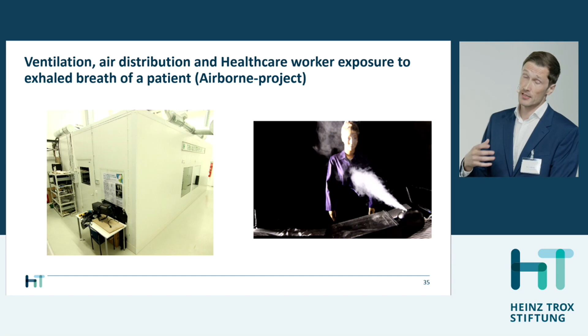And if it's not well mixed, what could we do about it? And how should we solve this problem, if there's any problem? So in this picture you can see an illustration of what can happen during a typical mixing ventilation case. There we have a mannequin simulating a patient lying on a bed, and then you have another mannequin simulating the healthcare worker standing next to the patient. And here you can see that the exhalation of the patient mannequin actually penetrates directly to the breathing zone of the healthcare worker.